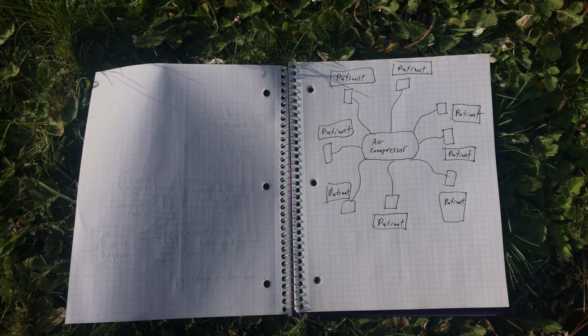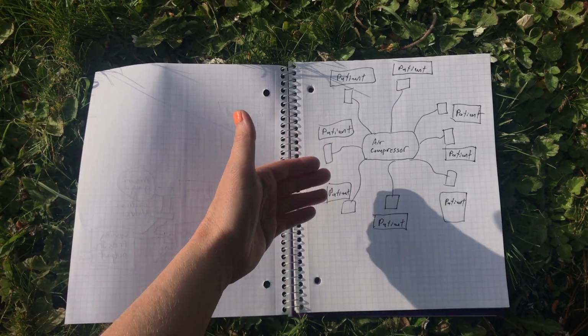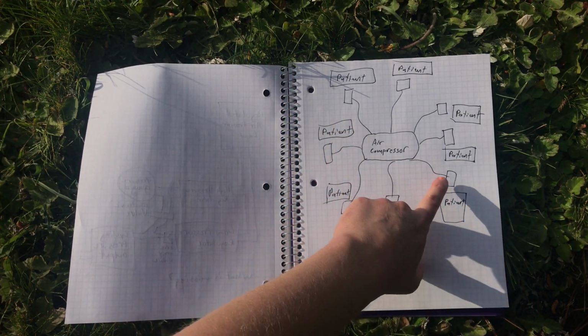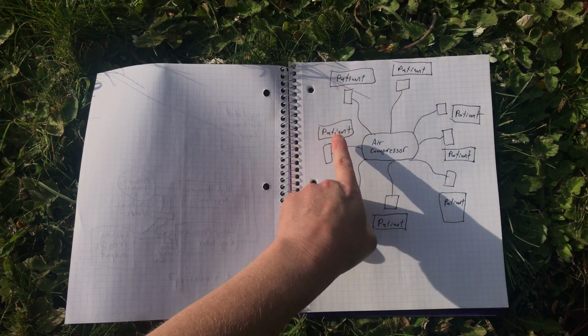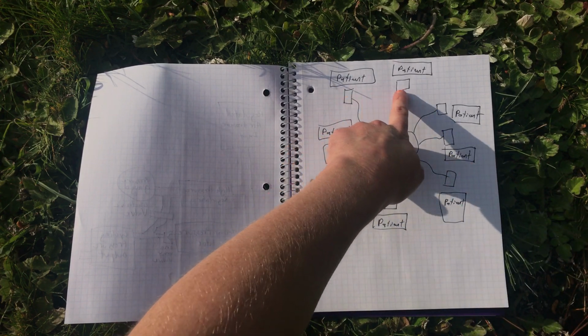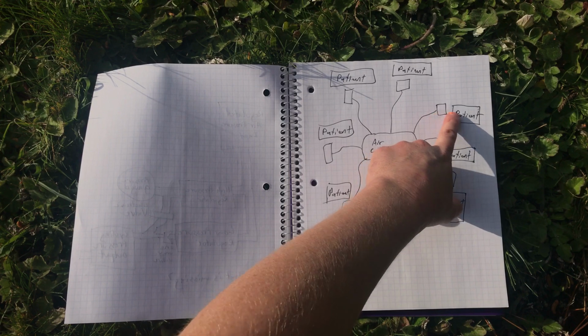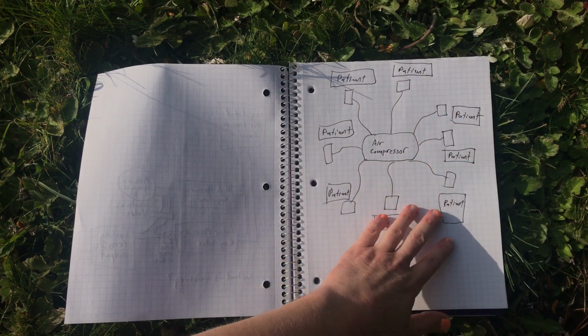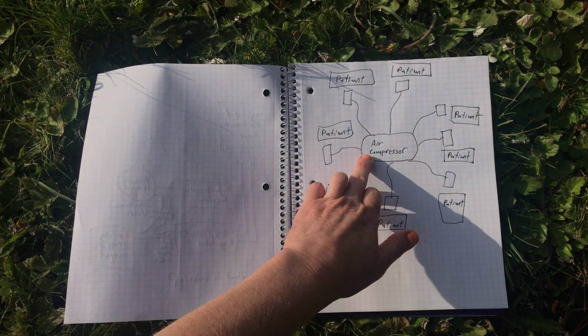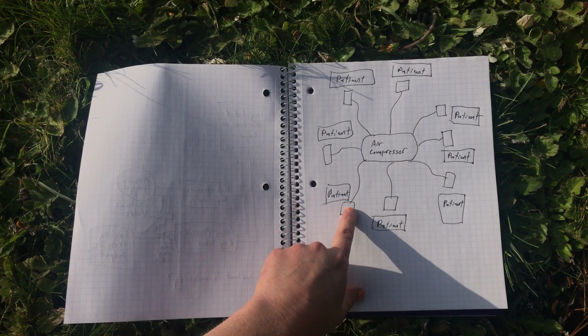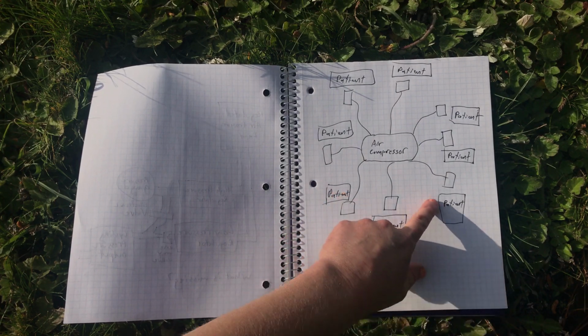Okay, so I'm going to start with this most abstract diagram here. One of the benefits of a machine that doesn't have the pump on board is that if you attach to potentially a regular air compressor, which are abundant devices, you could then supply many feed lines to a bunch of the devices I'm going to talk about. These would be basically a pressure manifold, which would then attach to normal intubation equipment, and you could serve with a single air compressor and a pressure-regulated feed, which is then modulated here, you could address many patients.